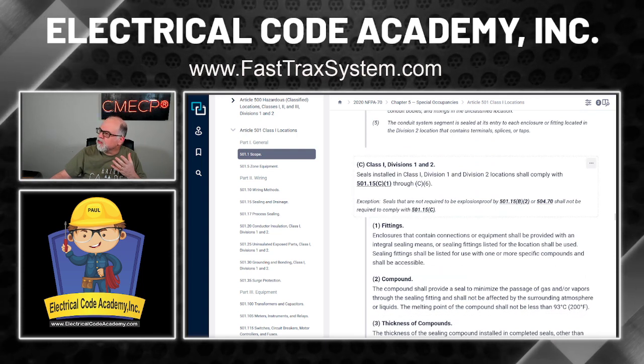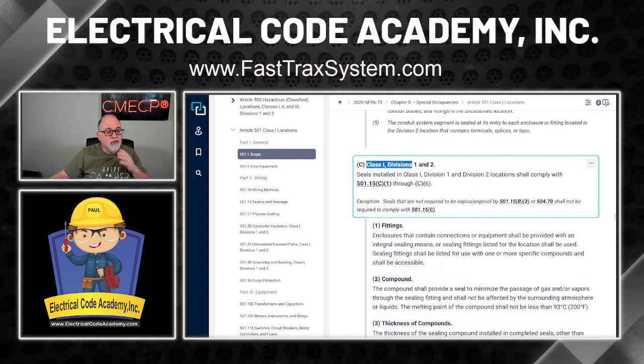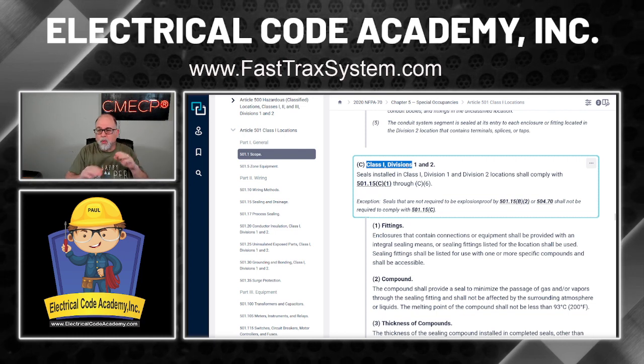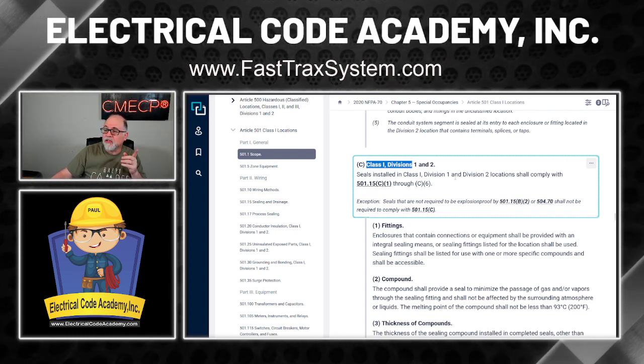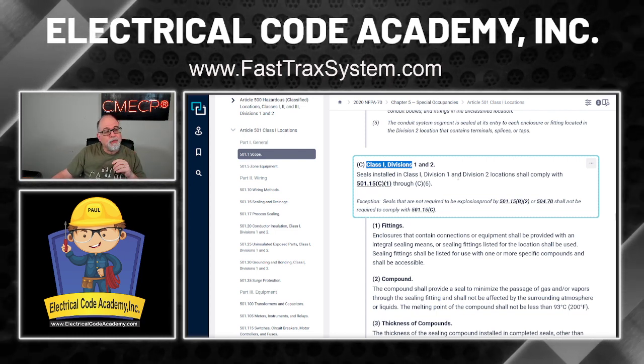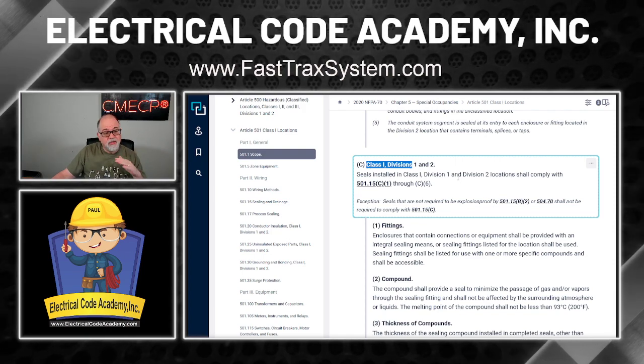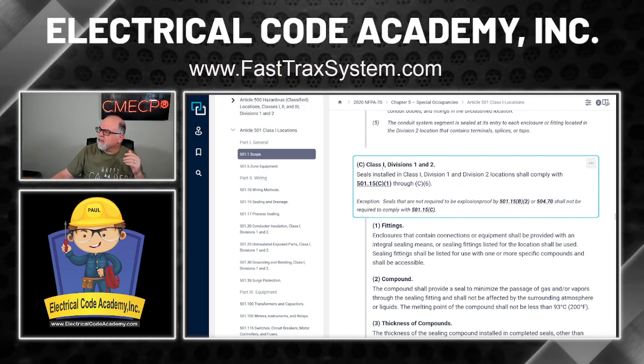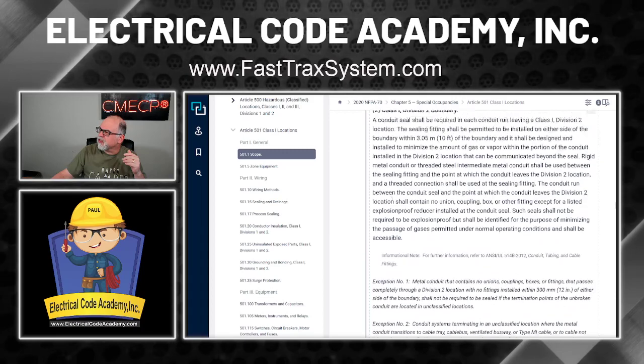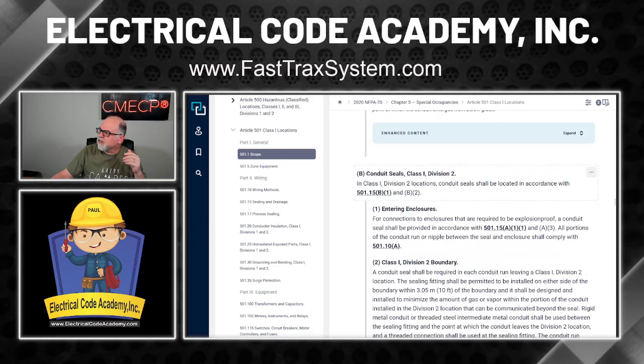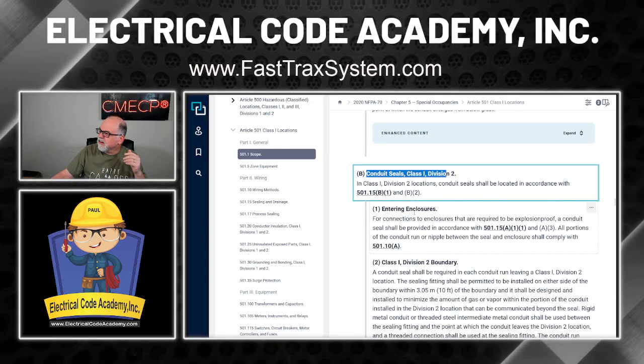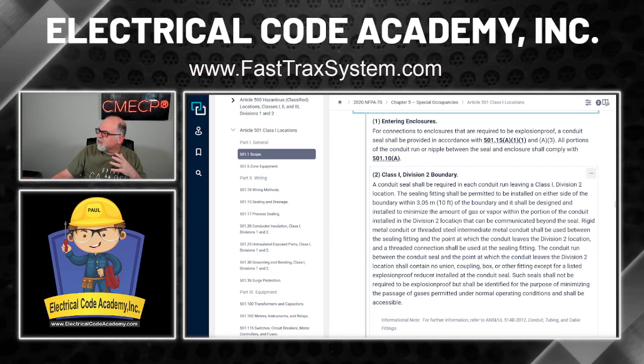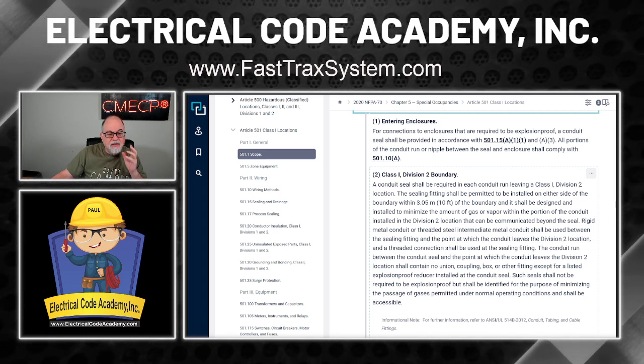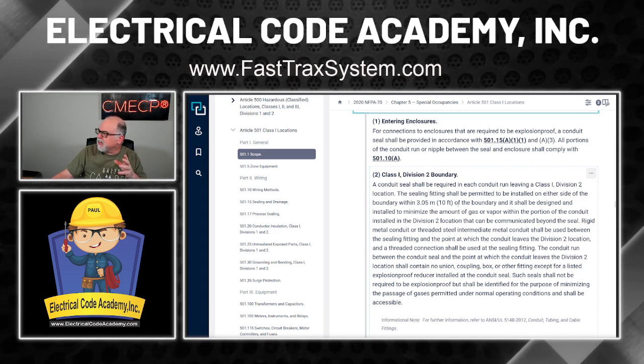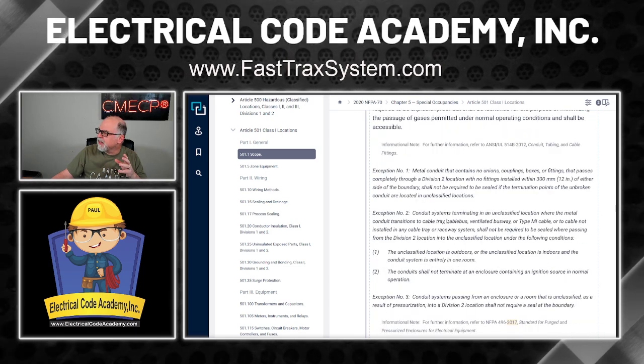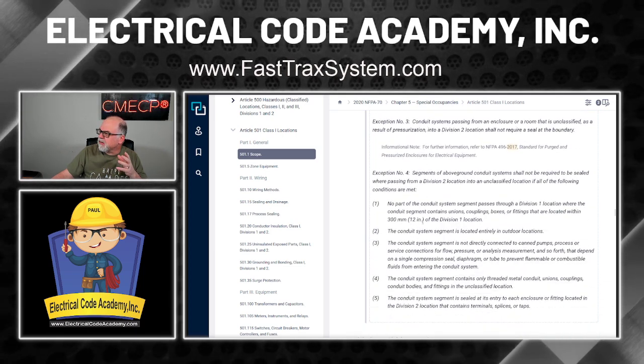And first thing you'll notice is we are dealing with Class 1 in Division 1 or 2. No, actually, the question didn't say whether it was 1 or 2 division, did it? It just says Class 1. So when I see this, and this is under the heading conduit seals, now is where I'm starting to look and see the answers, the inch values that are given. And I see nothing in here. Scrolling down inches, nothing matches our answer.